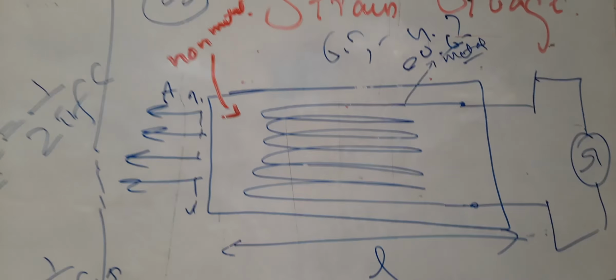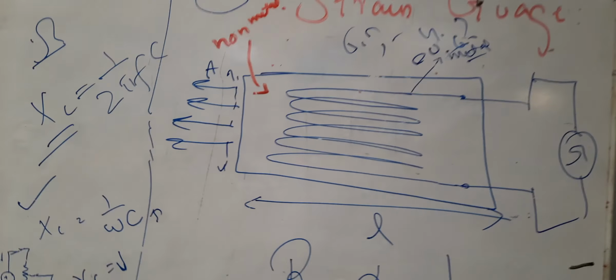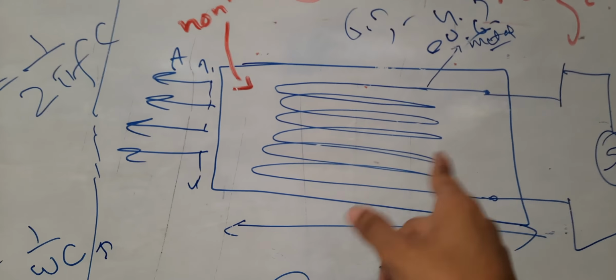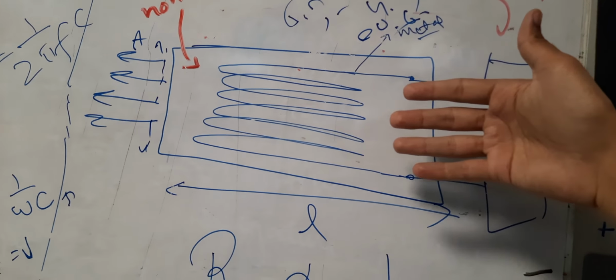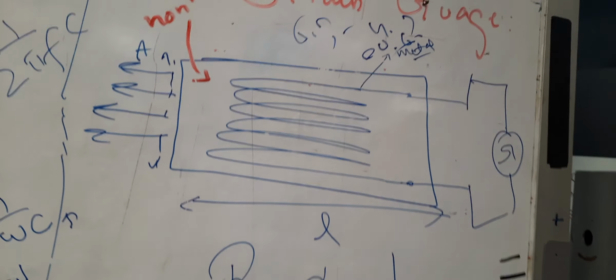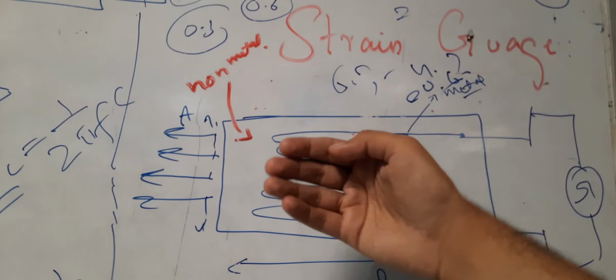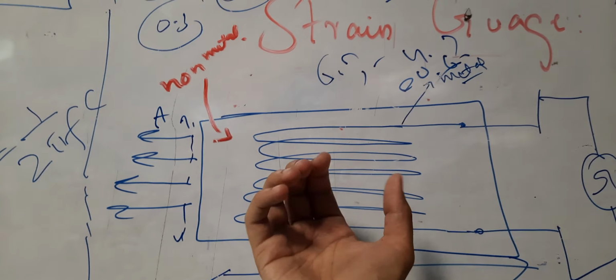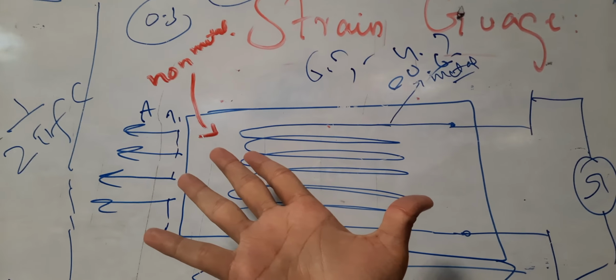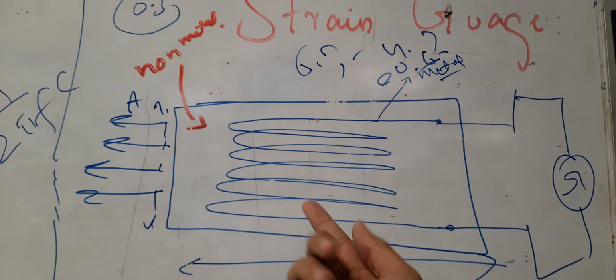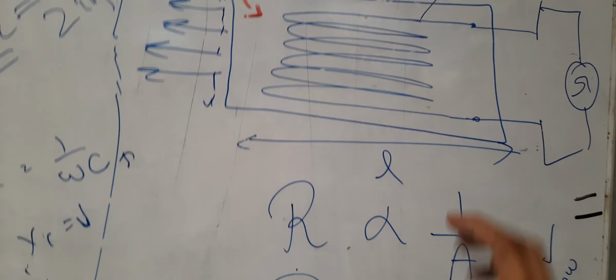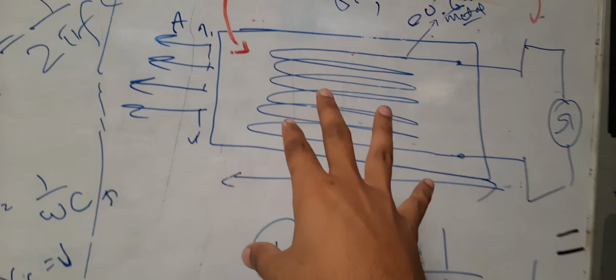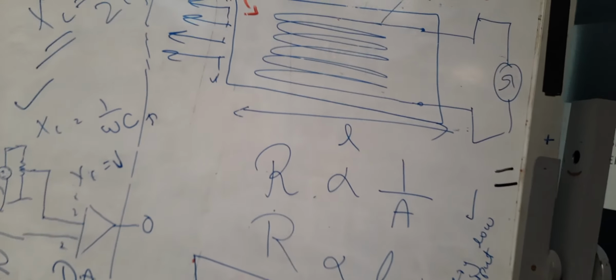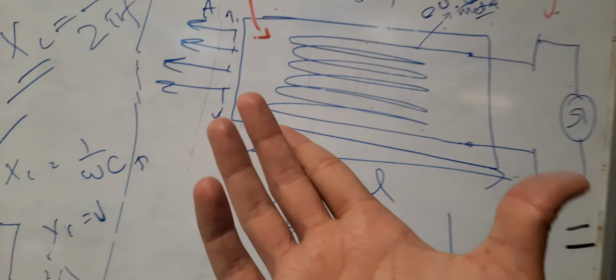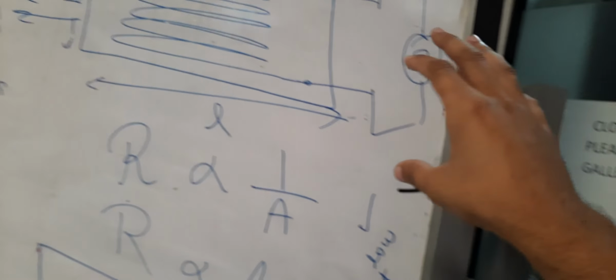Then we have the strain gauge, which is simpler in composition. Its base is non-metallic, with a metal wire on it. The base is elastic, and the metal is also somewhat elastic. When stretched, the length of the metallic wire increases while the cross-sectional area decreases, increasing the resistance of the strain gauge. So you can find the strain because it affects the resistance of the strain gauge.